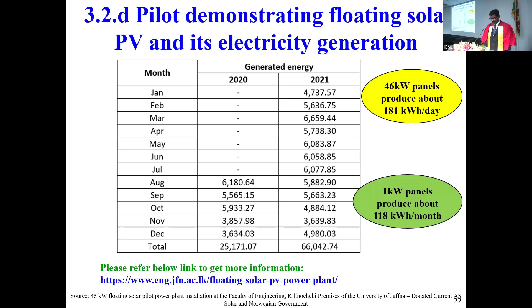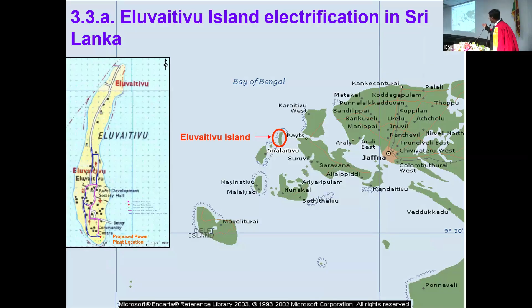Then there's the hybrid power plant made in Eluvaitivu North by the Ceylon Electricity Board, as one of the research outcomes from University of Peradeniya. Eluvaitivu is a small island, marked in red, about 3 kilometers by 650 meters wide, with about 125 families. There are 6 wind turbines of 3.5 kilowatts each, a 46 kilowatt rated solar panel, a 30 kilowatt small diesel plus a larger diesel plant, and a 110 kilowatt hour capacity battery bank. This was the plant at Eluvaitivu, almost like a small island with wind, solar, diesel, and battery.